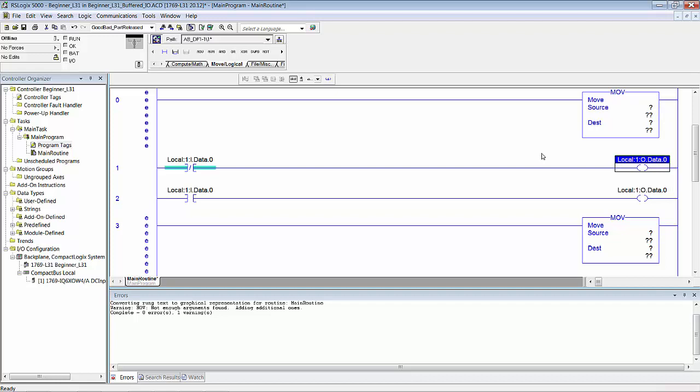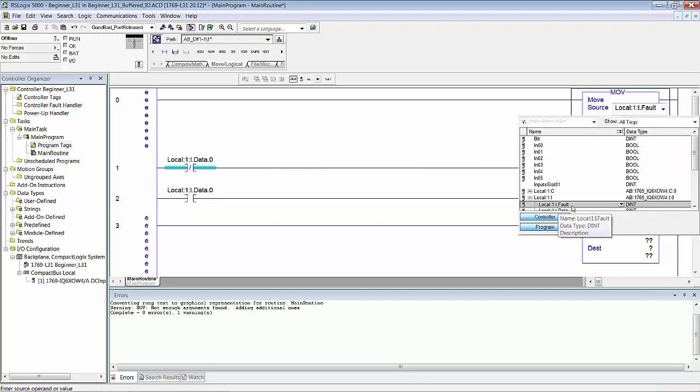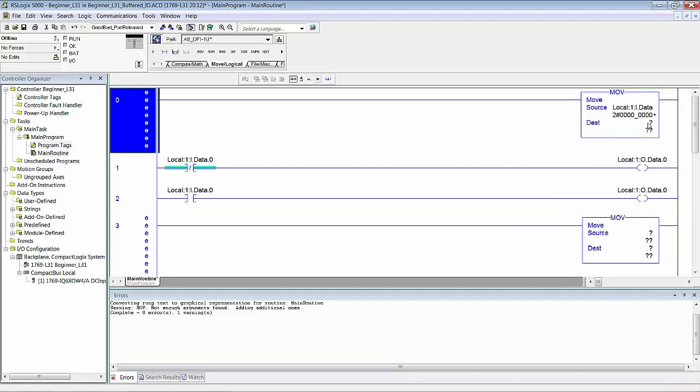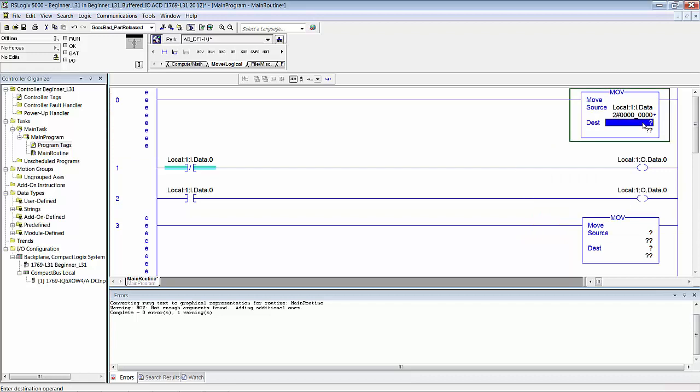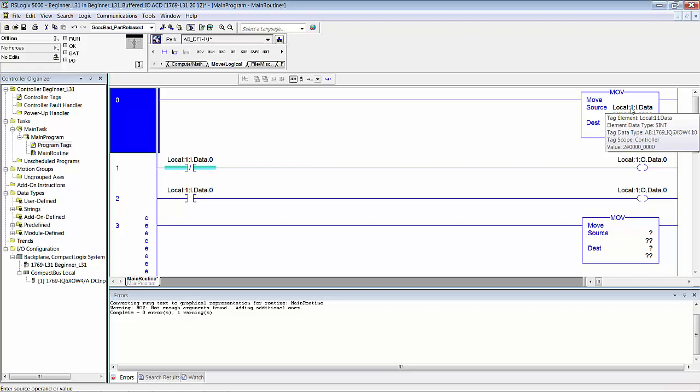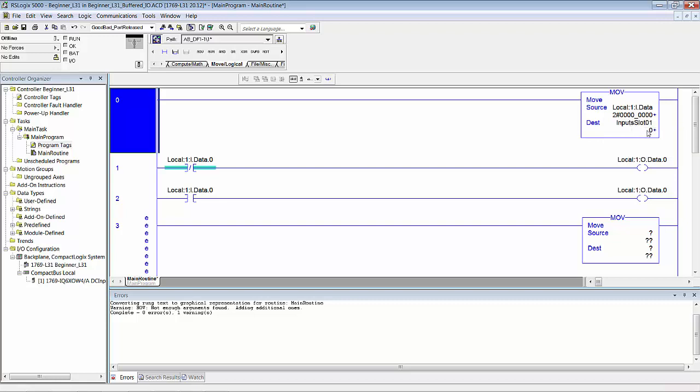Then I had you open the source on one of them. We'll do it the way we did it in the manual. Drop down and we want to move Local:1:I.Data. We want that whole word—it's actually a single integer. And we're going to move it into the tag that we created. Notice the type-forward. When I had just I-N it came up with the tag IN00. Add a P and it jumps right to the one that you want: InputSlot1. At the beginning of the program scan it's going to take and move that I/O input data word into this tag that we created.